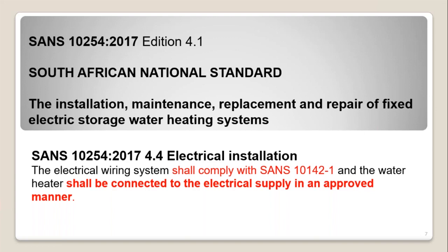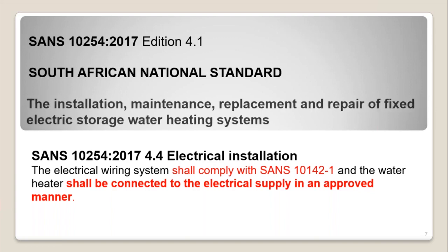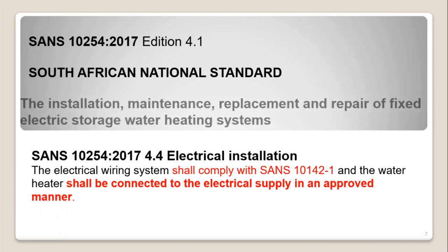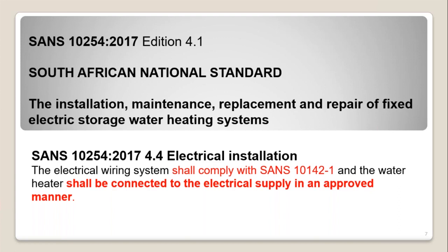In our installations standard, SANS 10254, we can see at clause 4.4, it addresses the electrical part where it says the electrical wiring system shall comply with SANS 10142 and the water heater shall be connected to the electrical supply in an approved manner. Okay, next one, Herman. What this will mean is that the electrical installation, what we do on a replacement, will have the following components. Next one, Herman.